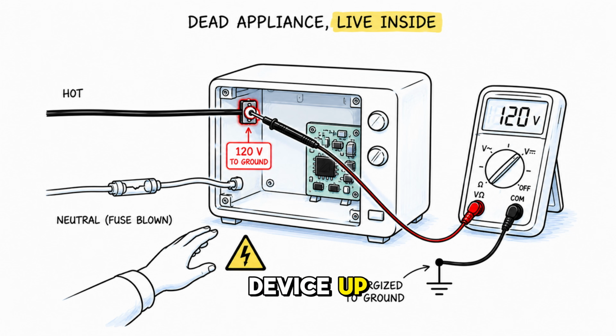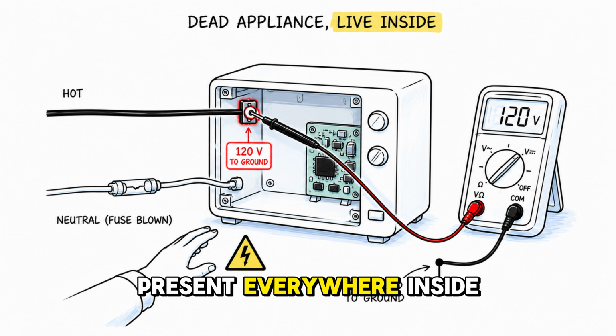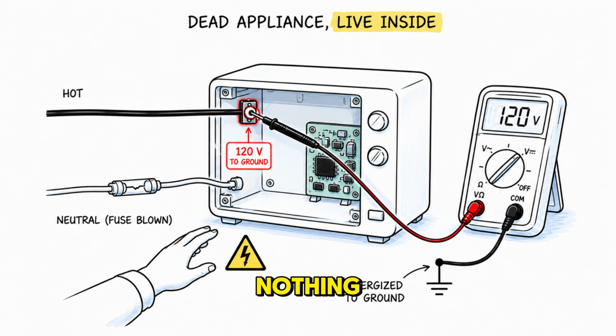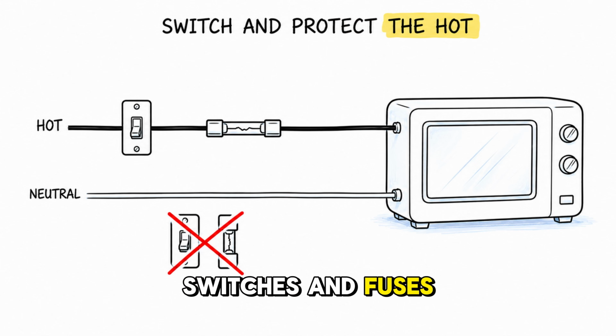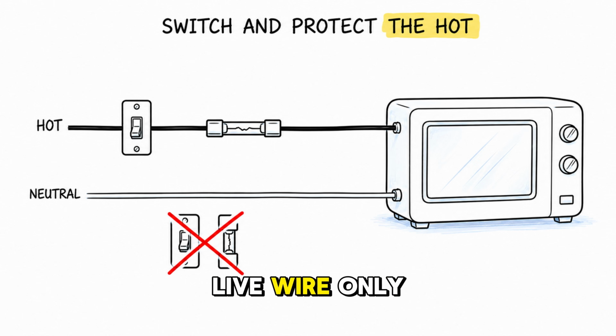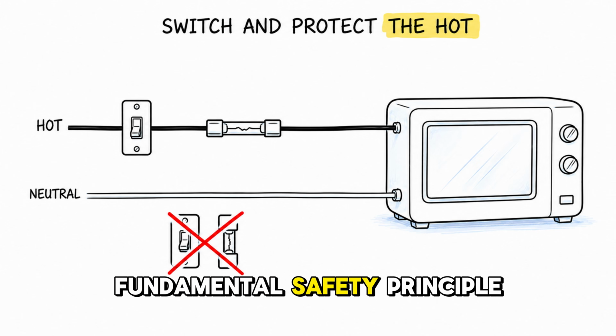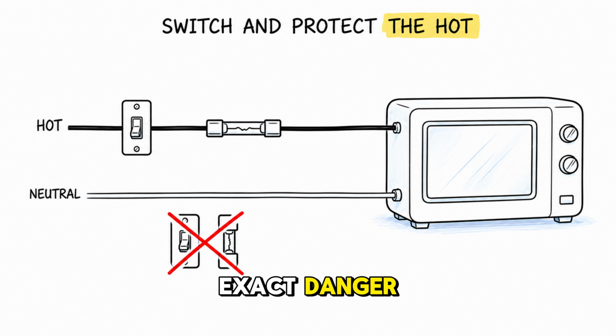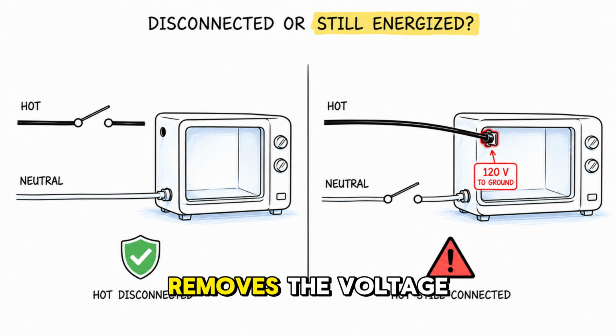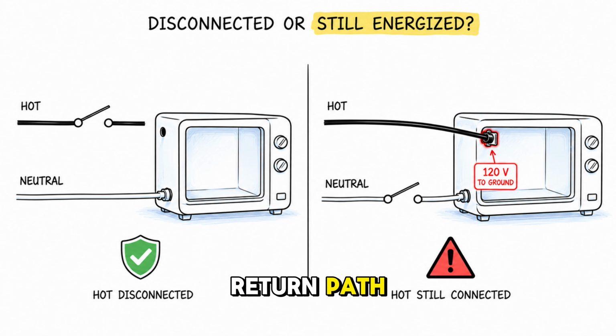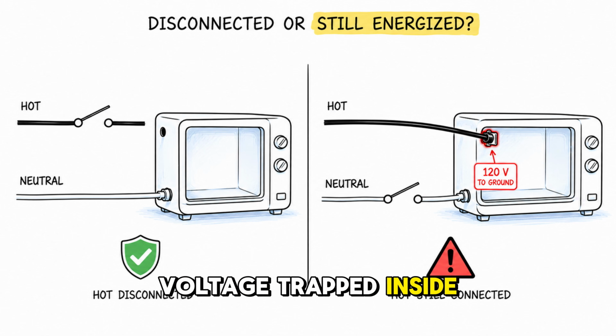They open the device up. Live voltage is present everywhere inside. The fuse protected nothing. It simply created a hidden live appliance that appears completely dead. Switches and fuses must always be placed in the live wire only. This is not a suggestion. It is a fundamental safety principle based on this exact danger. Switching the live wire removes the voltage source from the appliance entirely. Switching the neutral removes only the return path, leaving the full voltage trapped inside.